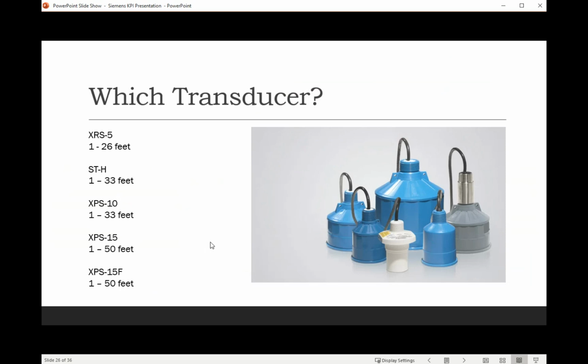All right, so let's get into transducers. All right, so with Siemens, we have about 5 transducers that work with the Hydroranger 200. They're all different lengths, different feet, and they're all kind of specialized for certain applications. Where, let's say the XRS5 is our small little guy right here, and this is more optimized for open channel flow, high accuracy applications, and where then the STH is material PVDF or ETFE, so those chemical totes, chemical tanks, anything along those lines. It's got a 2-inch NPT connection on the bottom, or you can use a standard 1-inch NPT connection on top.